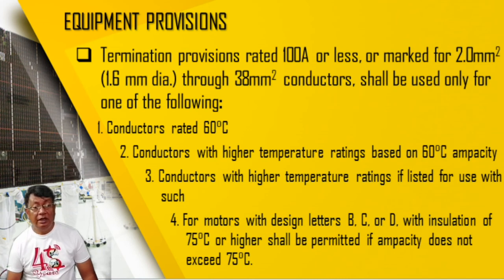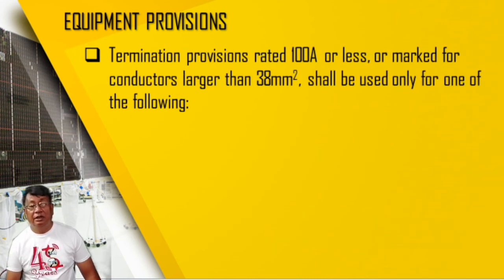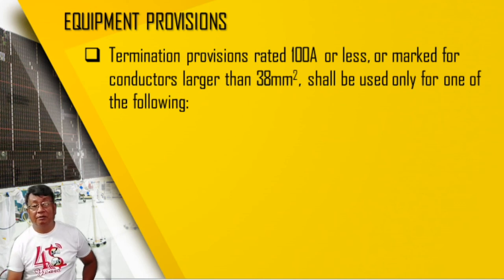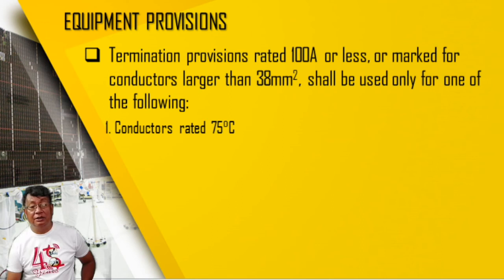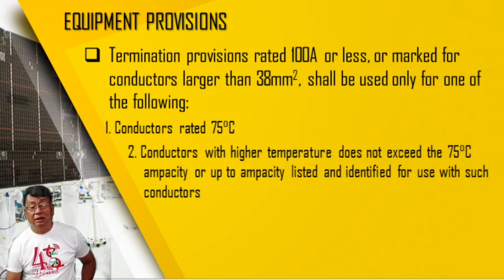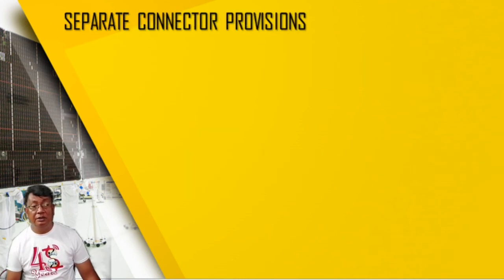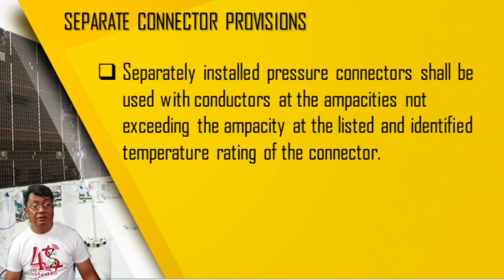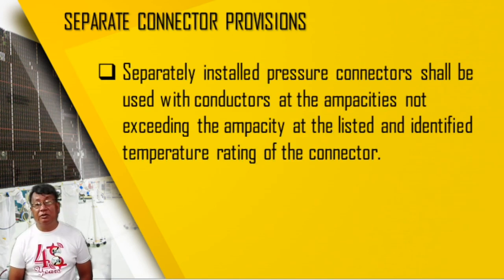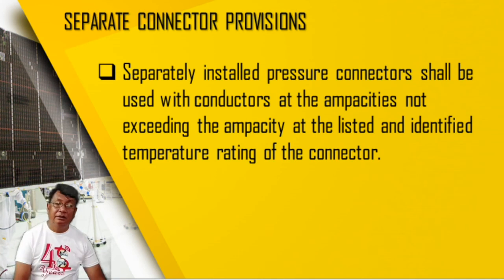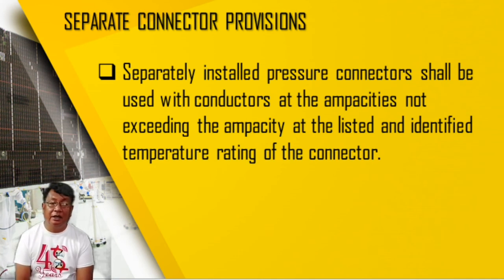Okay, so next we have termination provisions rated over 100 amperes, or marked for conductors larger than 38 millimeter squared, shall be used only for one of the following. So we have conductors rated 75 degrees Celsius. We have conductors with higher temperature ratings, provided the ampacity does not exceed the 75 degrees Celsius ampacity, or up to their ampacity if listed and identified for use with such conductors. Separate connectors. Okay, separate connectors here. Separately installed pressure connectors shall be used with conductors at the ampacity not exceeding the ampacity of the listed and identified temperature rating of the connector. Okay, so this is all about the conductor ampacities, no? Conductor ampacities.